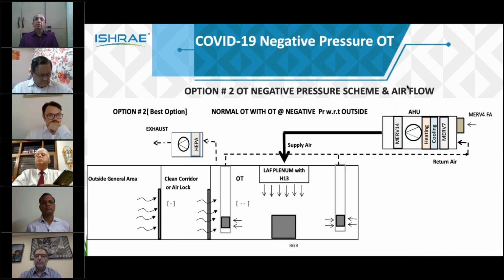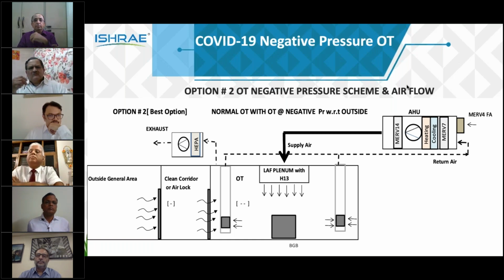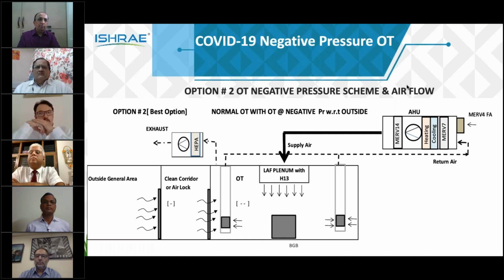Here we don't tamper with the outside area. What we do here is install an exhaust system with a HEPA filter, and you take the air out from the operation theater itself, if that's feasible, and throw it out into the atmosphere. So here what happens is you get the air from the outside area, it passes through the airlock and then into the OT, and the OT is now under negative pressure, and the outside areas don't get affected by whatever is happening inside the operation theater with the patient or otherwise. So these are the two options which are safe enough to be implemented, and you have to go case by case on what is physically possible to install. We'll go to the next slide.